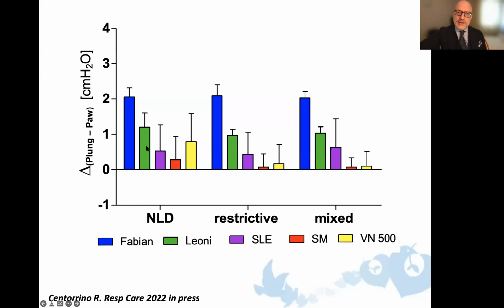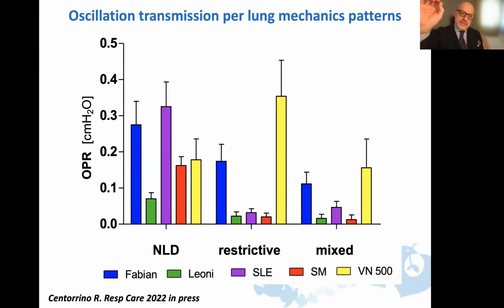While all the other ventilators have a variability in this sense, and some of them are similar to Fabian, some other a little bit less. But the most important thing is to be focused on the oscillation pressure. So the oscillation transmission rather than the simple steady mean airway pressure transmission. So in order to understand the oscillation transmission, and so to measure it, we are going to use a parameter that is called OPR, meaning oscillatory pressure ratio. That's a classical parameter in HFO mechanics.